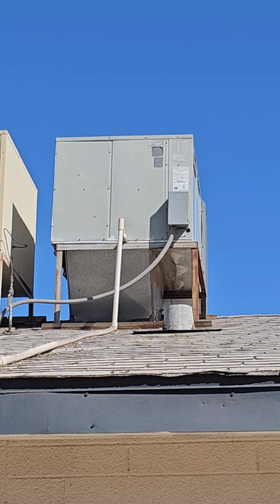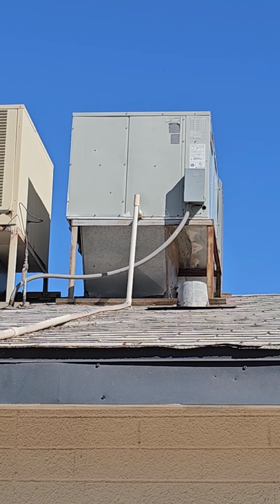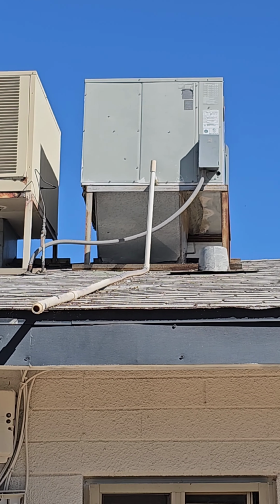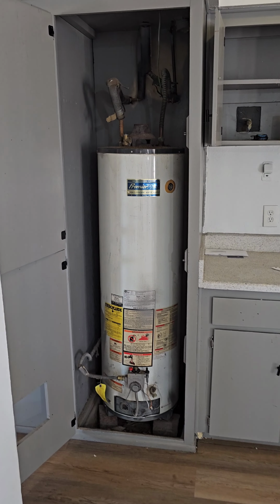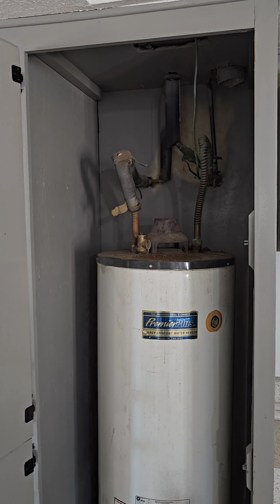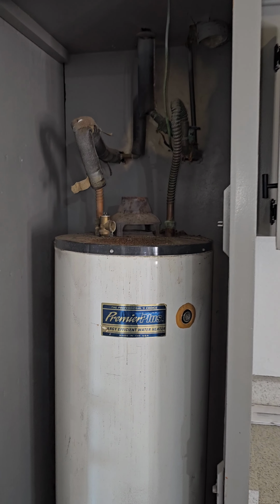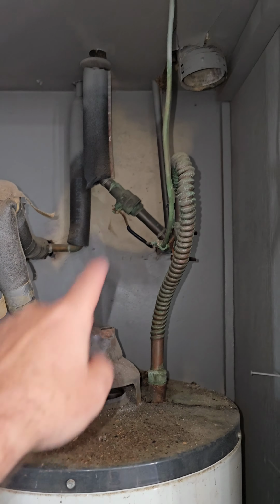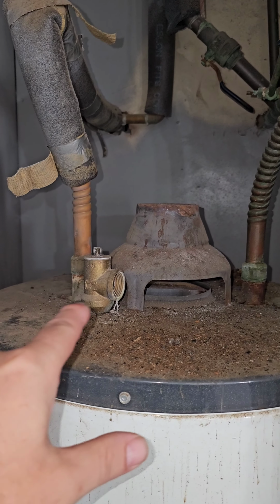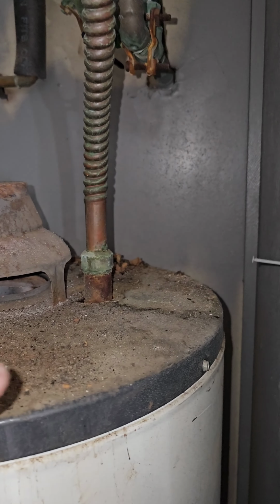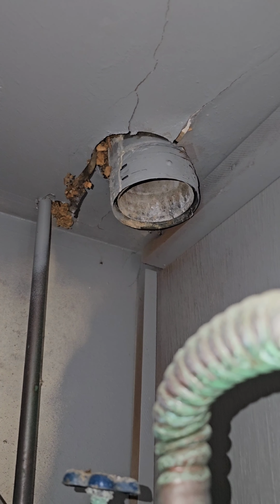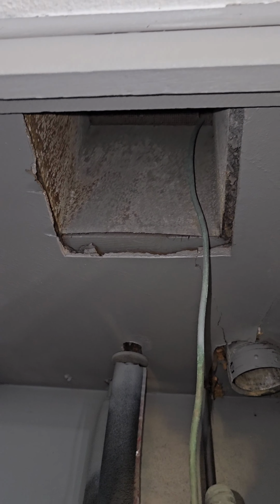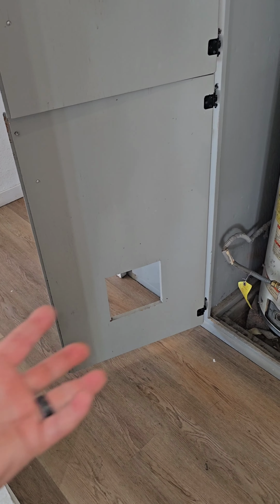Because we have a heat pump up on the roof, there's no gas line up to it, so there's no need for one. The only gas appliance in this house is the water heater, which is from 2006, and codes were better back then. We don't have an exhaust flue for the combustion gases, no TPR discharge line, corrosion around the lines, signs of previous leaks, insulation poking through the vent, and inadequate combustion air at the top. You're actually using house air for combustion.